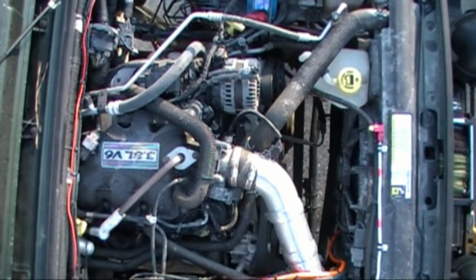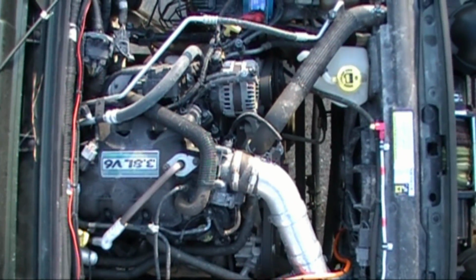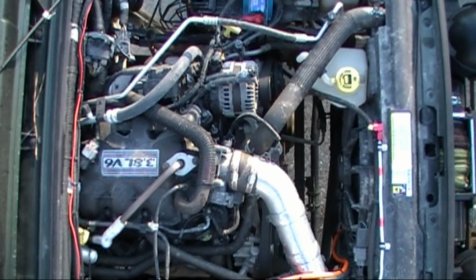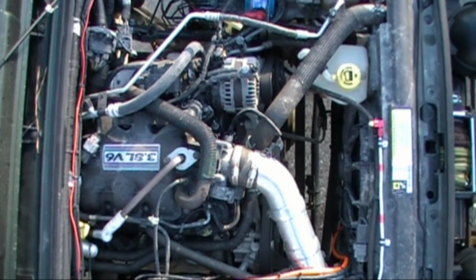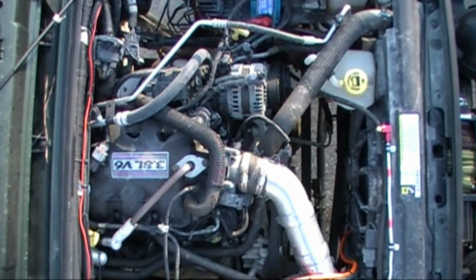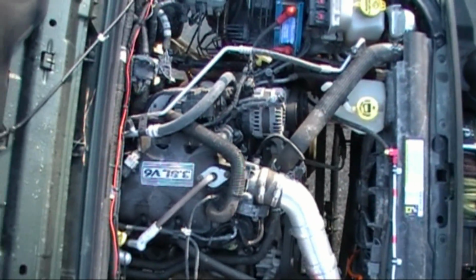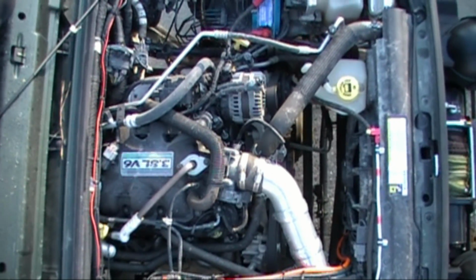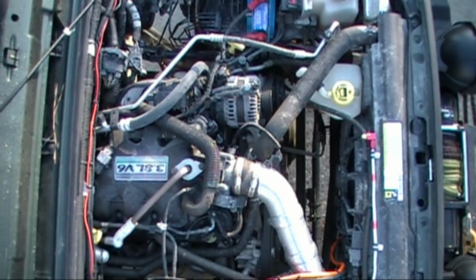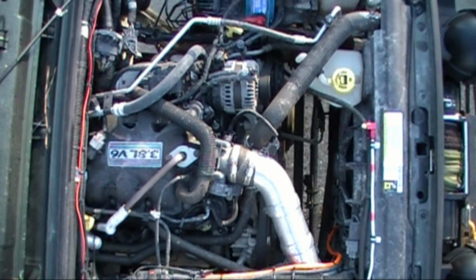And now we're going to demonstrate just the primary nozzle in the engine compartment. You can see the nozzle to the right hand side, the little bright red square. Most of your vehicle fires are going to happen inside your engine compartment. Either fuel or fluid is going to drip onto your exhaust manifold and ignite, electrical wires are going to short out and ignite, or even branches and twigs get jammed up in there onto your exhaust manifold and catch fire. I want to show you exactly how much spray and how much coverage I'm getting from just this one nozzle. Setting off the ColdFire fire suppression system, same as before, pulling out the safety flag and pushing or pulling the handle depending on your application.